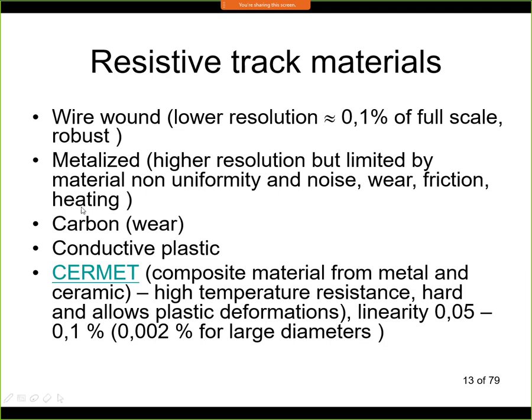The second possibility is a metalized layer — you take a base material like ceramics or plastic, deposit a metalized layer, and use it as the resistive track. Compared to wire wound, this has higher resolution — basically infinite resolution — but it is limited by material non-uniformity and noise. This layer can also be damaged by wear, friction, or heating, so it is a little less robust than the wire wound sensor.